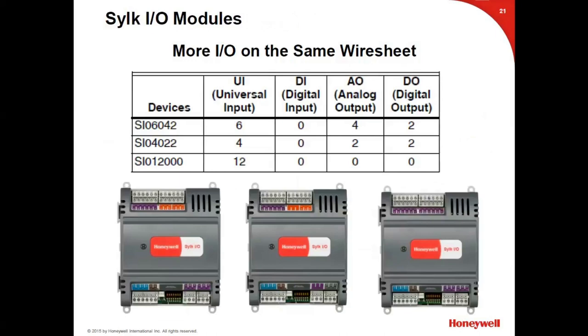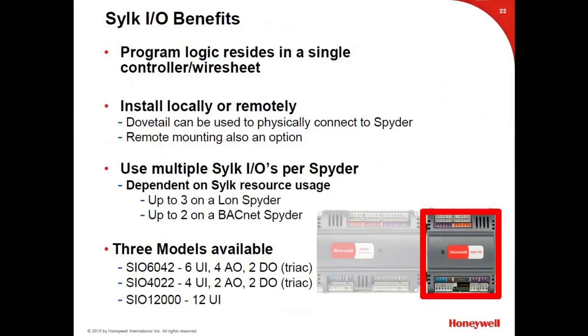Here are the Sylk I/O modules. We kept the same naming convention: SIO, followed by three models — 6042, 4022, and 12000 (meaning 12 universal inputs and no other I/O). The program logic resides in the controller — the I/O modules are essentially dumb I/O that you connect to the controller via the Sylk bus. You can mount them right next to the controller or remote mount them. We're limited to three on a LON Spyder and two on a BACnet Spyder due to processor and memory constraints.